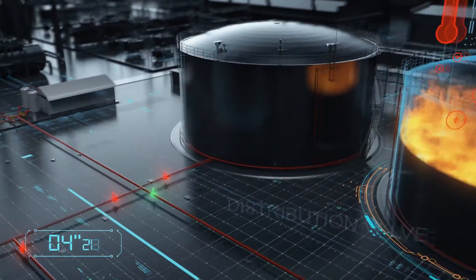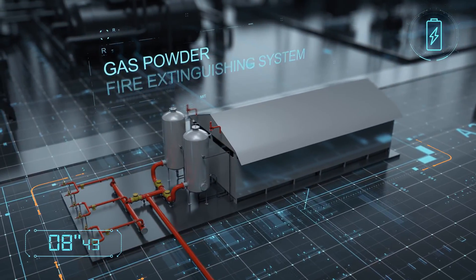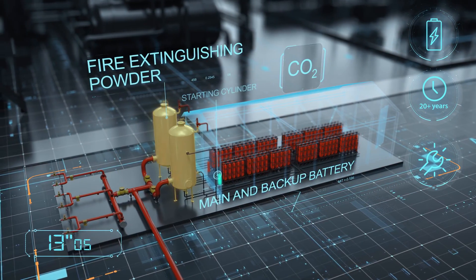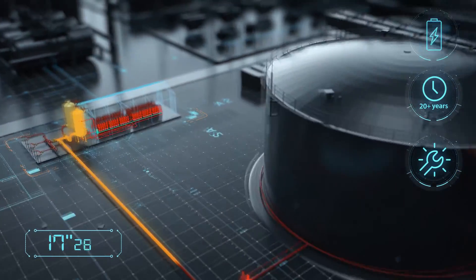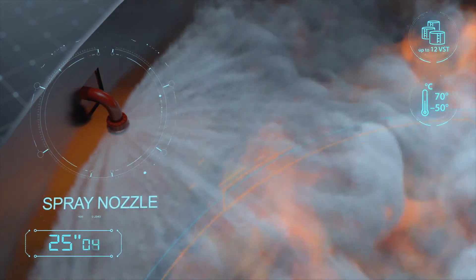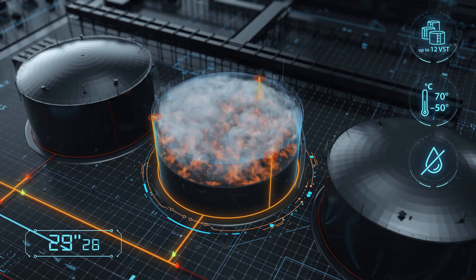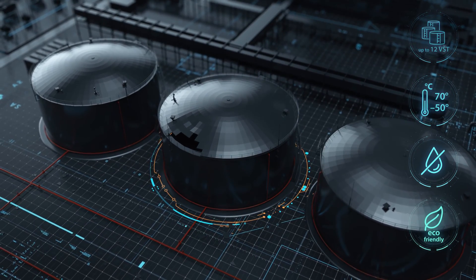The gas powder mixture is supplied via pipelines to the tank and ejects through spray nozzles of patented design. It requires no water. The system may be used in adverse climatic conditions, and the system's minimum lifetime is 20 years. Capital and operational costs are much less compared to traditional foam fire extinguishing systems. Bi-Zone can protect tanks of up to 100,000 cubic meters.